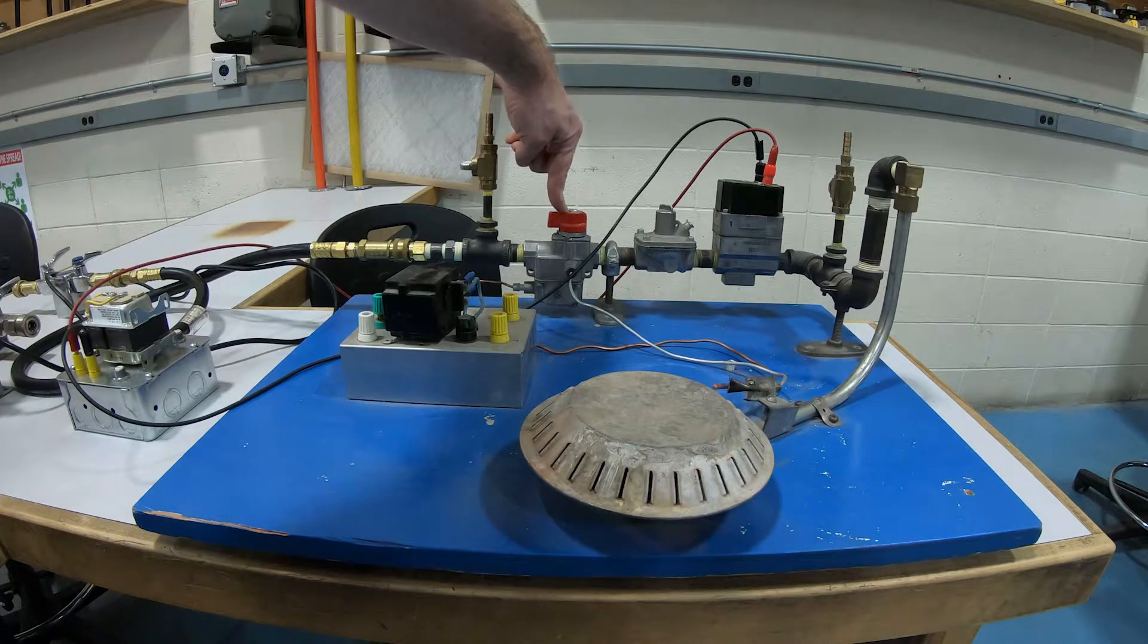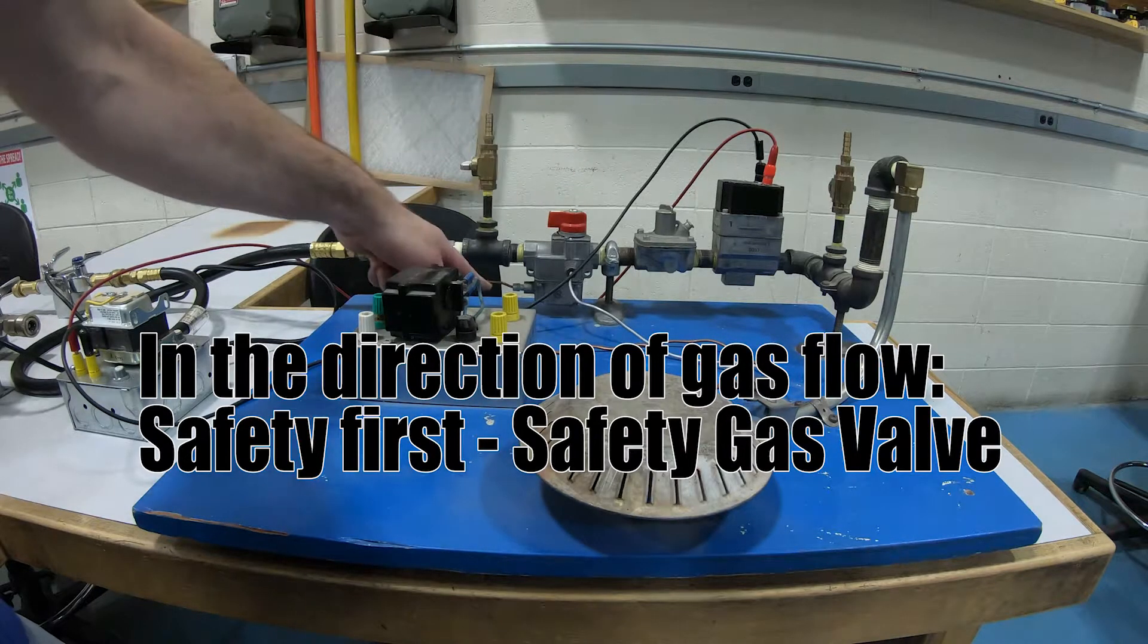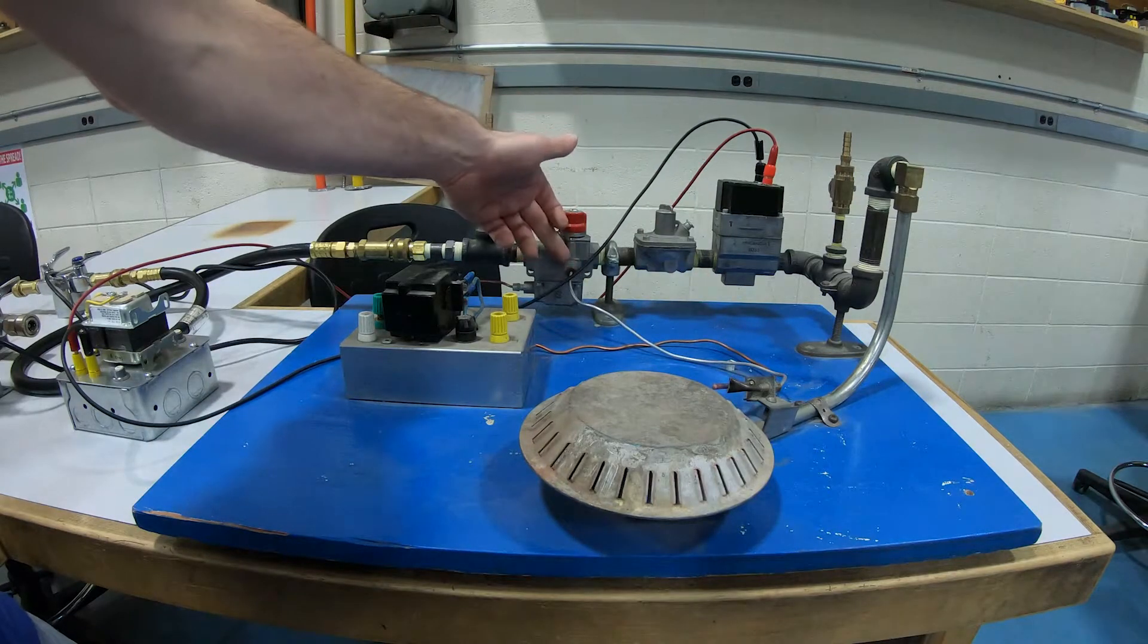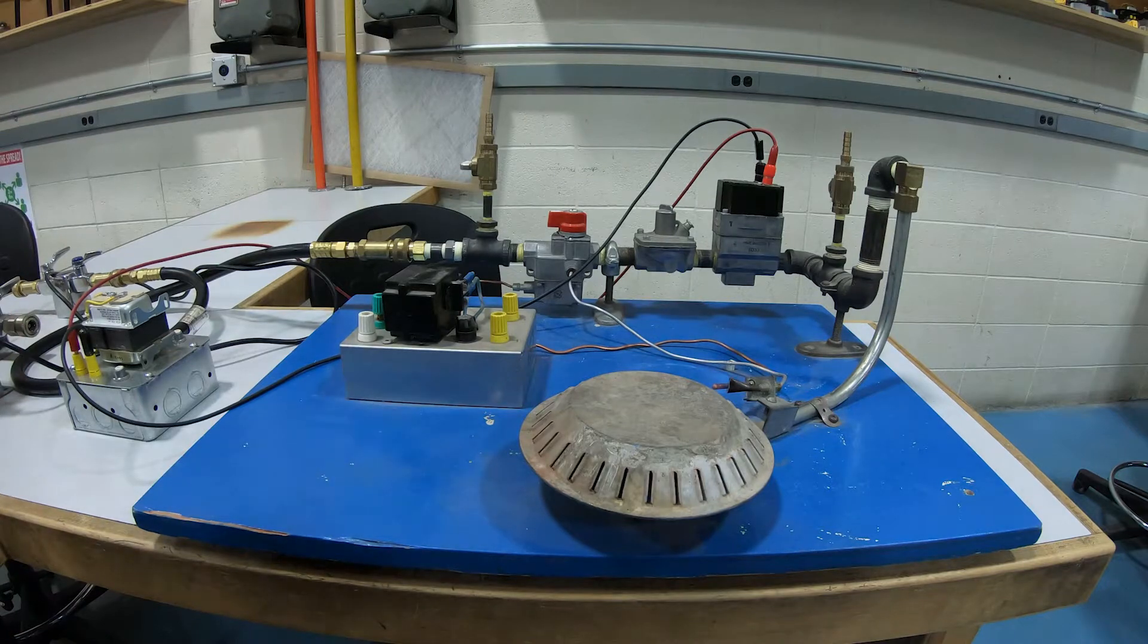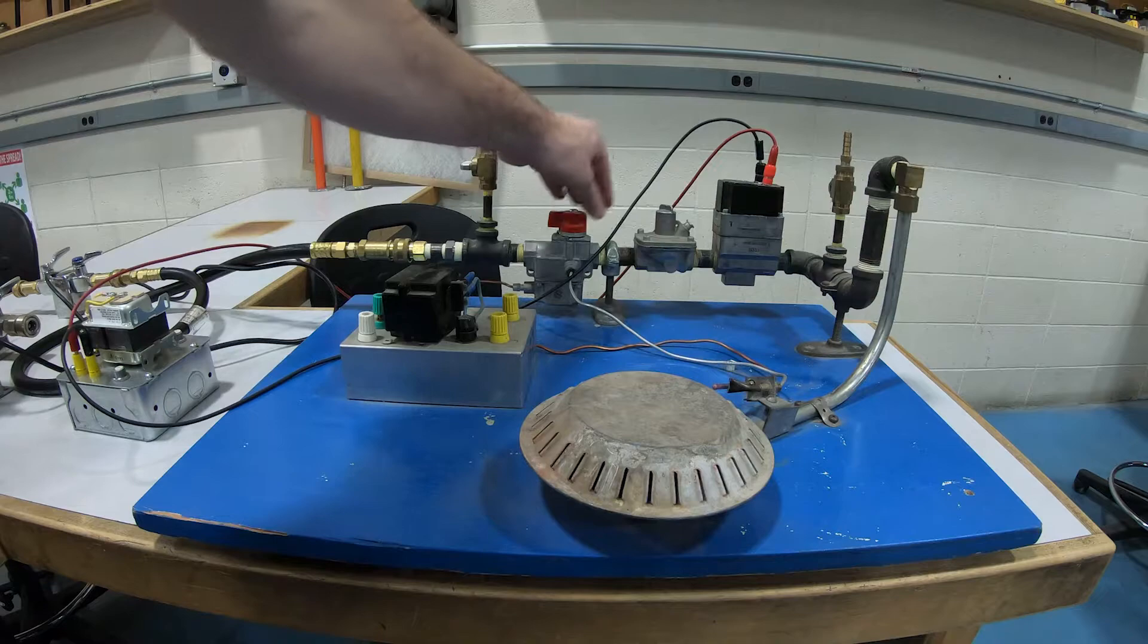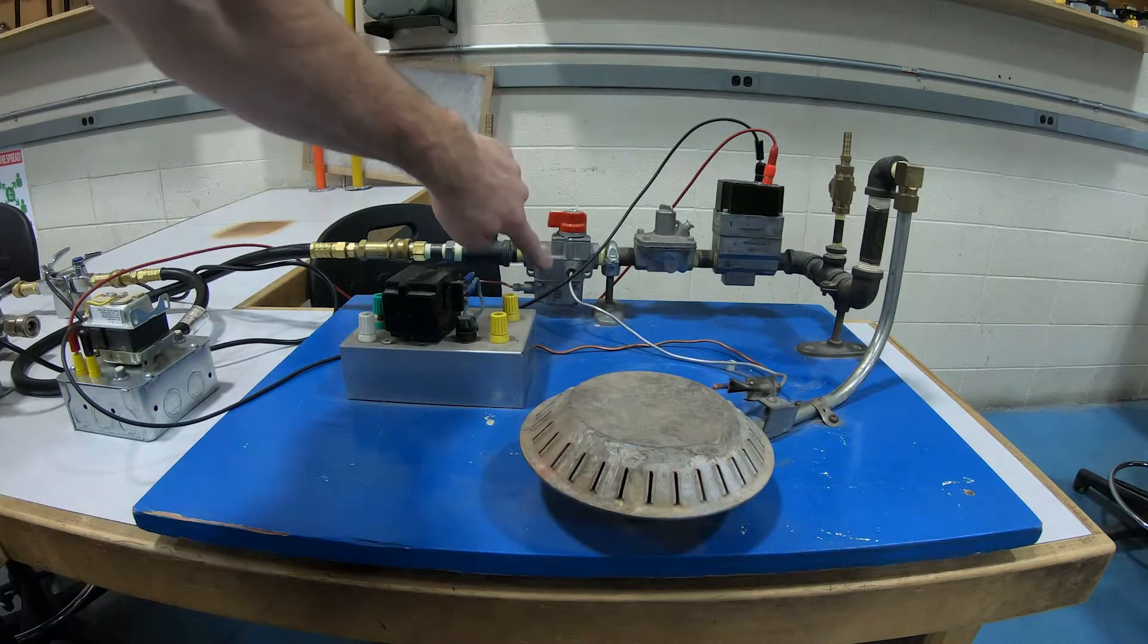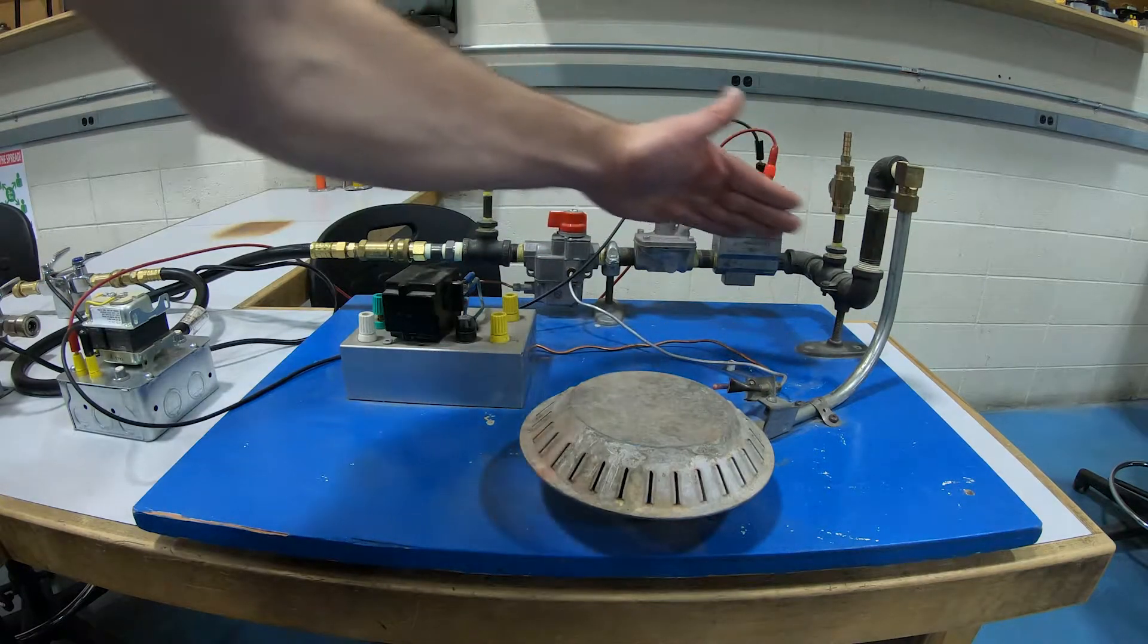Always we have safety first. This is a gas safety valve. We've got a thermocouple that goes into there and this is a pilot tube going to the pilot light. So that is our typical thermocouple protected assembly. If this thermocouple goes out or the pilot goes out, this gas valve that's built in here shuts off and no gas can flow through to the rest of the burner.